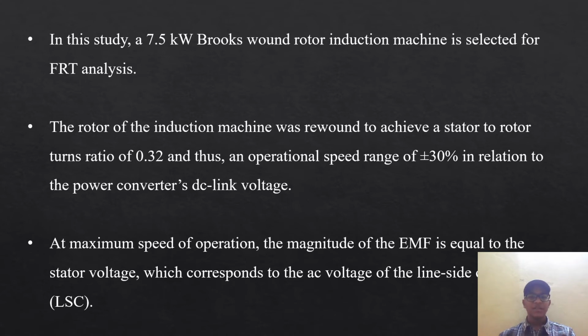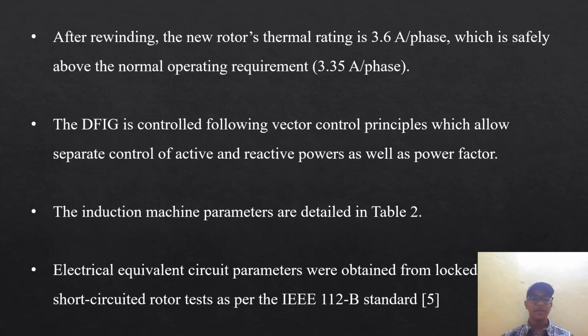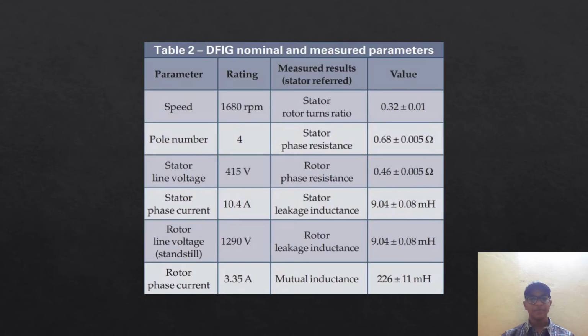The rotor of the induction machine was rewound to achieve a stator to rotor turns ratio of 0.32. Thus, the operational speed range is plus or minus 30% in relation to the power converter DC link voltage. At maximum speed operation, the magnitude of the rotor EMF is equal to the stator voltage, which corresponds to the voltage of the line side converter (LSC). After rewinding, the new rotor's thermal rating is 3.6 amperes per phase, which is safely above the normal operating requirement of 3.35 amperes per phase. The induction machine parameters are detailed in Table 2. Here is Table 2 of DFIG nominal and measured parameters.